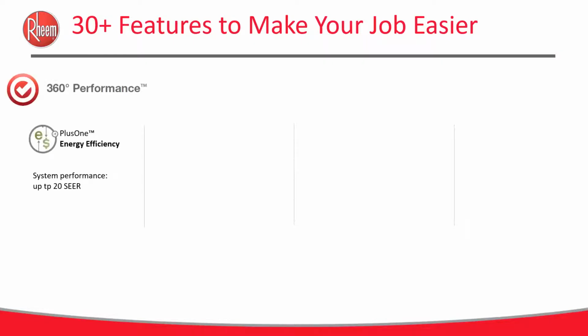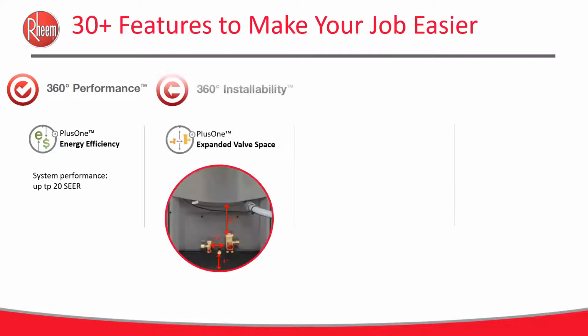30 plus features to our cooling platform over our previous generation. Plus one energy efficiency, which means 20 SEER through 5 tons, and HSPF of 11 through 5 tons, composite base, fan, optimized fan orifices, louvered coil protection, and some of the other features we've discussed. 360 installability. So expanded valve space, 15-inch control box, high-low voltage hookup and external gauge ports, integrated lift receptacles, and no sharp edges.